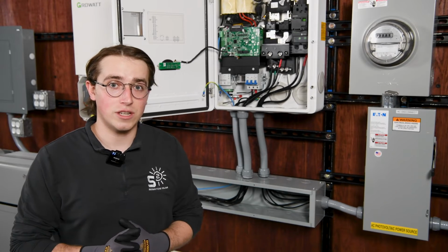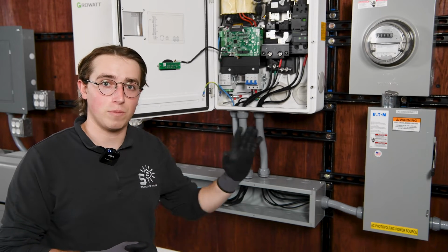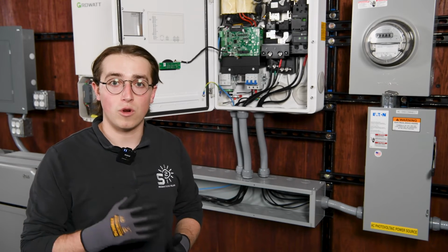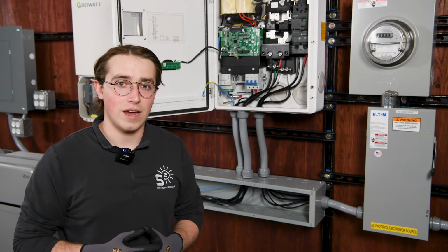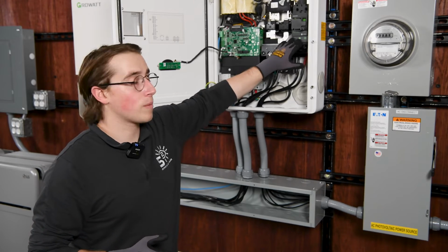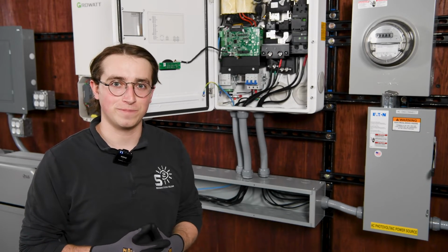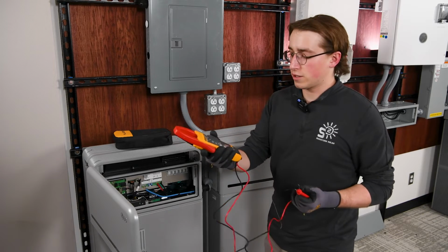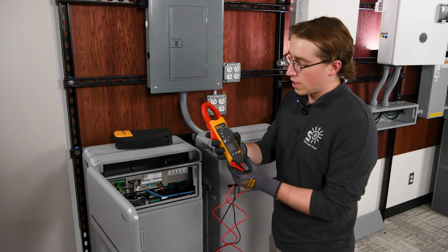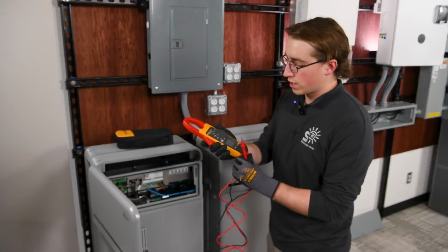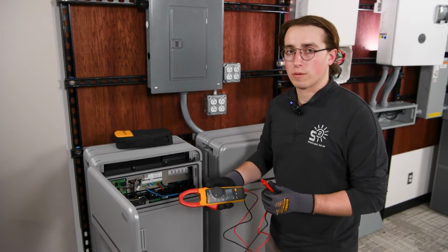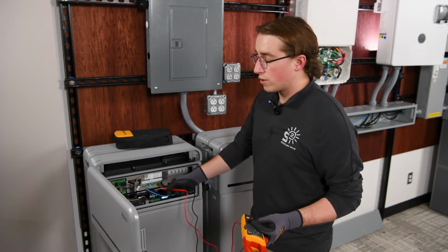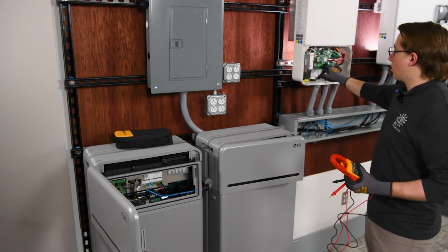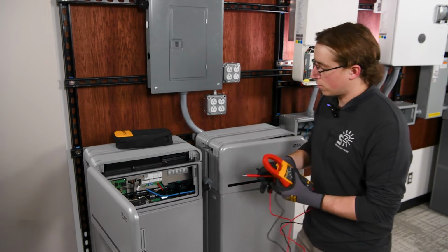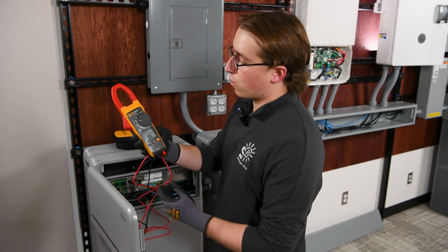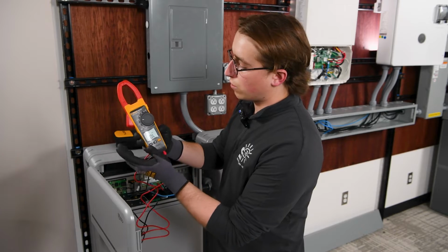Next process in this commissioning setup, we are going to turn on our batteries and supply power to the inverter and the SYN. We'll commission everything through the Growatt app, and then we'll power on the system fully, supplying power from the grid and powering a few loads. As a safety precaution, and something that I like to do before I power on any circuits, I like to do a continuity or an ohms test to make sure that I'm not getting any cross polarity across the battery terminals, and to make sure that the positive on my battery is making good contact with the positive terminal on the inverter. So with that, we'll just switch our multimeter to our ohm or continuity reading.